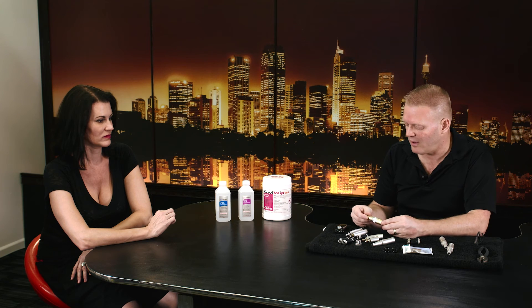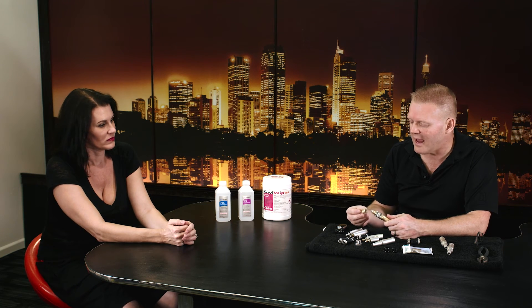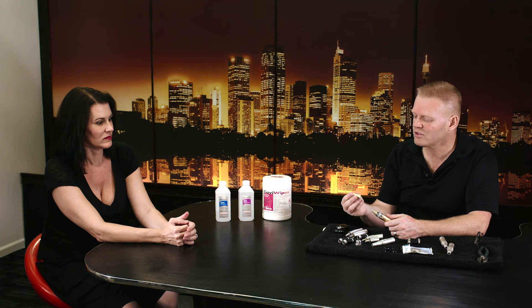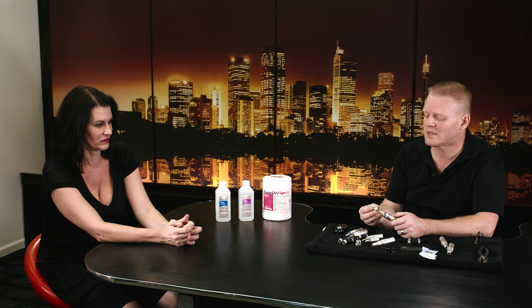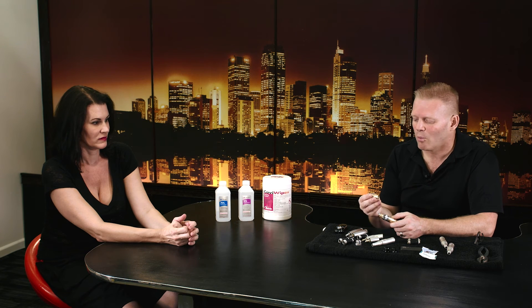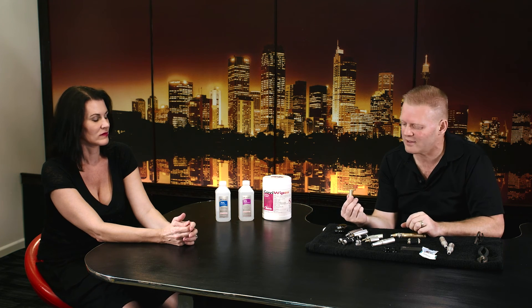A pen design was developed where the cartridge doesn't leak — it has seven different safety features — and you can also remove the nose cone and autoclave-sterilize it. That is the ultimate safety factor. If fluid somehow managed to defeat the cartridge — which hasn't been demonstrated — there's still a fail-safe: you remove the nose cone, and it can be high-level disinfected; the internal components can be sterilized.